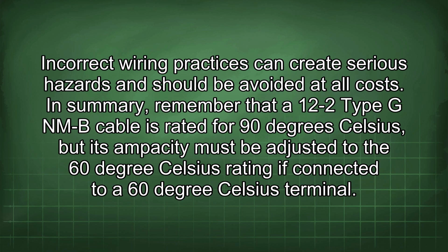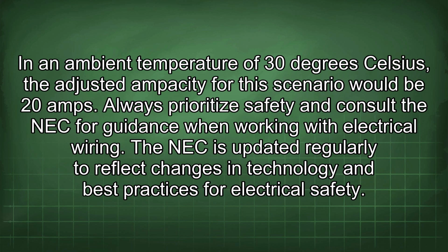In summary, remember that a 12/2 type NM-B cable is rated for 90 degrees Celsius, but its ampacity must be adjusted to the 60 degrees Celsius rating if connected to a 60 degrees Celsius terminal. In an ambient temperature of 30 degrees Celsius, the adjusted ampacity for this scenario would be 20 amps. Always prioritize safety and consult the NEC for guidance when working with electrical wiring.